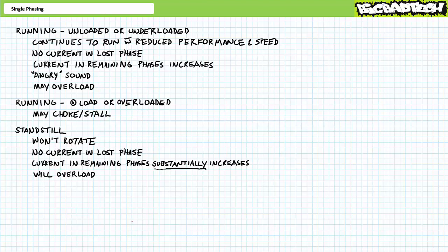In each of these scenarios, a single phased motor draws no current in the lost phase and more current in the remaining phases. An extremely simple means of troubleshooting a motor suspected of single phasing is to take three current readings using an amp clamp. Current drawn in the remaining phases will be high; current in the lost phase will be non-existent. Lock it out, tag it out, and fix the problem.